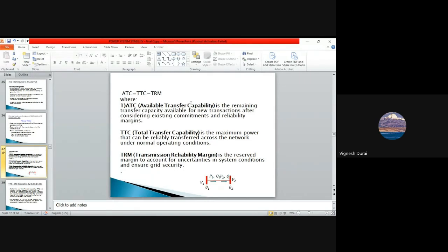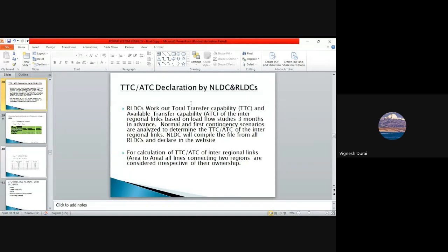If there are some outages, some line goes into some problem, it means that an outage is declared in the line. This ATC should be monitored by us. Okay, the amount which can be transferred physically will be monitored by us, and this ATC will have some standard which is decided by RLDC. RLDC works out the transfer for interstate lines, like from Karnataka to Tamil Nadu or Maharashtra, somewhere, any line.